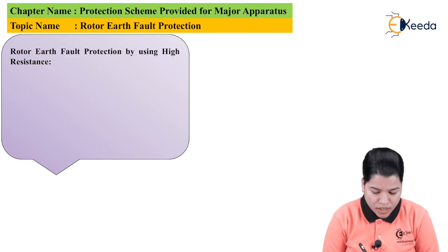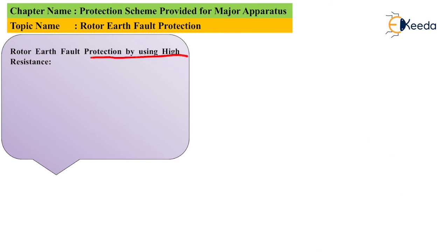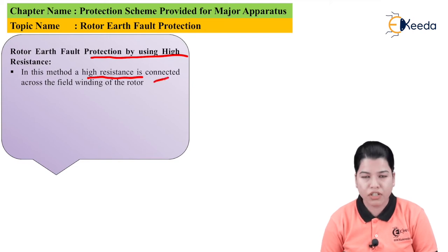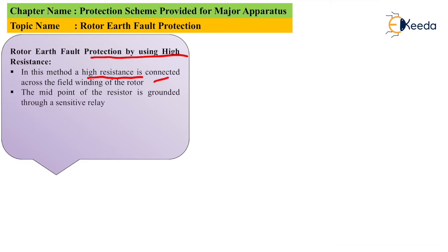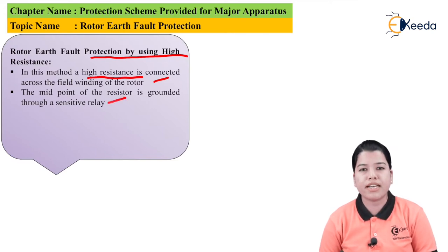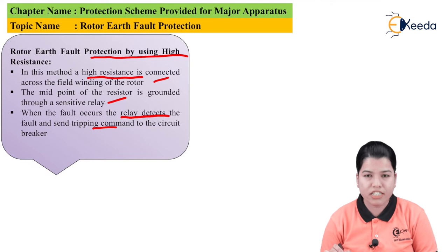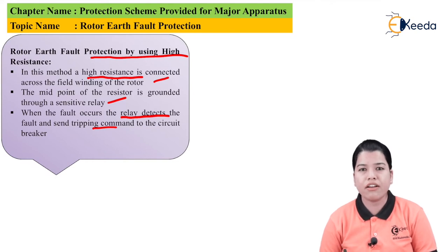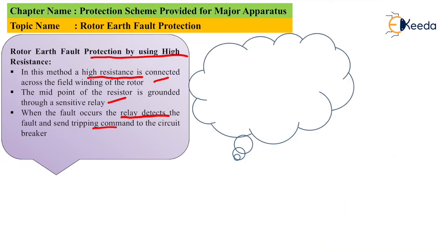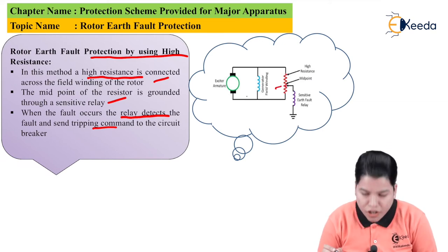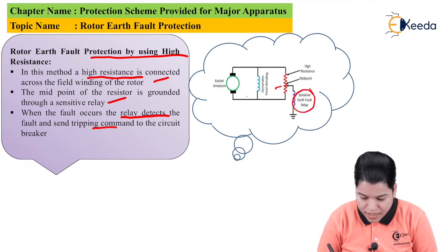Our first method is rotor earth fault protection by using high resistance. In this method, a high resistance is connected across the field winding of the rotor. The midpoint of this resistor is grounded through a sensitive relay. When a fault occurs, the relay detects the fault and sends a tripping command to the circuit breaker. The figure shows the arrangement of the high resistance for rotor earth fault protection, where the midpoint of the resistance is grounded through a sensitive earth fault relay.